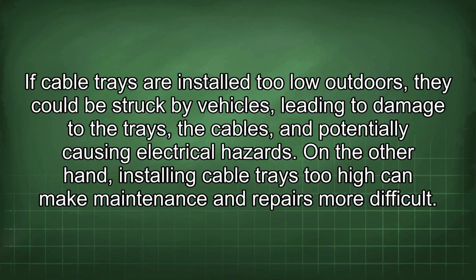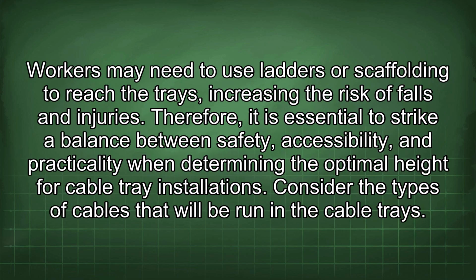On the other hand, installing cable trays too high can make maintenance and repairs more difficult. Workers may need to use ladders or scaffolding to reach the trays, increasing the risk of falls and injuries. Therefore, it is essential to strike a balance between safety, accessibility, and practicality when determining the optimal height for cable tray installations.